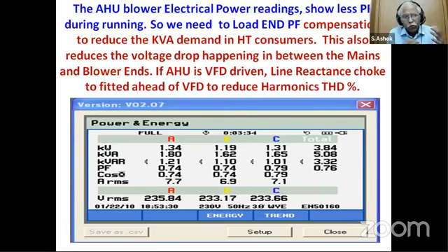And if the blower has been used with a retrofit of VFD, we find in many air conditioning units, especially on compressors, blowers and pumps, many of the VFDs inject a lot of harmonics, THD, at the incoming side. If this has to be curbed, definitely we need to go for a line reactor or choke at the input of the VFD. You see to it, it is a mandatory provision to be done in all your installations, because this has become mandatory.